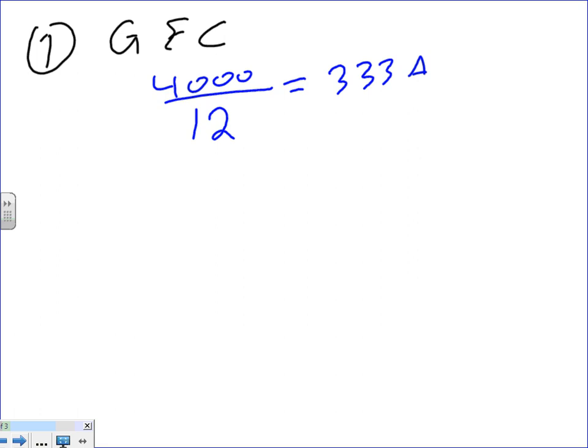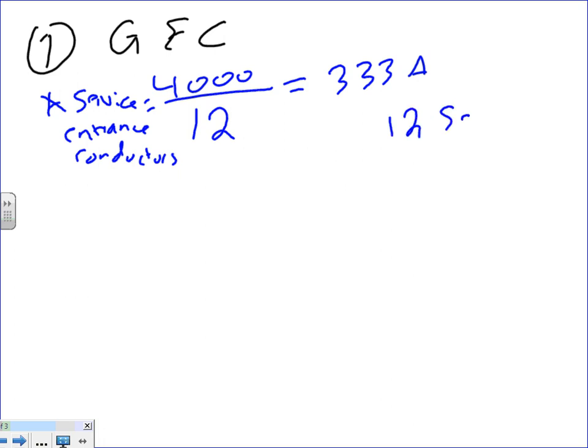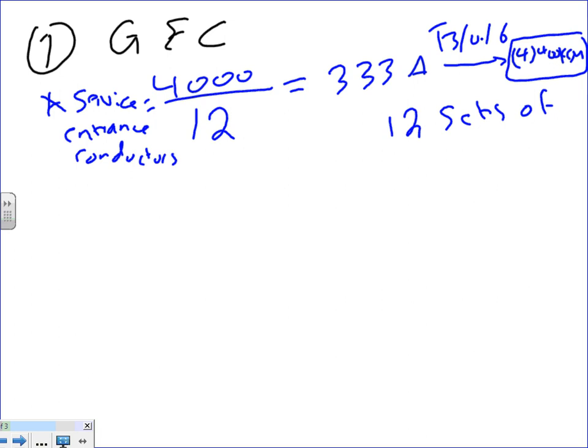And then to run it, I need 12. This is service entrance conductors. You need to find the service entrance conductors, guys. I decided to parallel 12 runs, as you guys have done. So I have 12 sets. If you take this to the 310.16 table, this will get you, if I did that one run, 400 kcm, 4 conductors, 400 kcm. That's step number one: size the service entrance conductors. That will get you a 400 kcm right here. 400 kcm, 4 of them. Why 4? 4 conductors, 400 kcm.